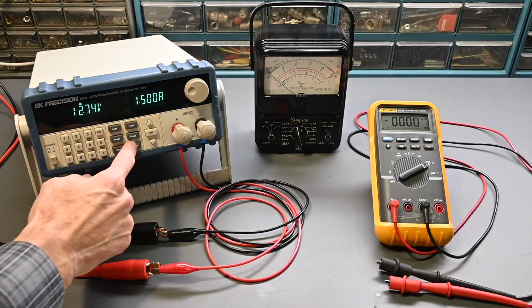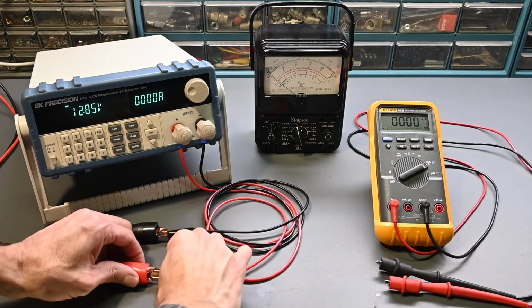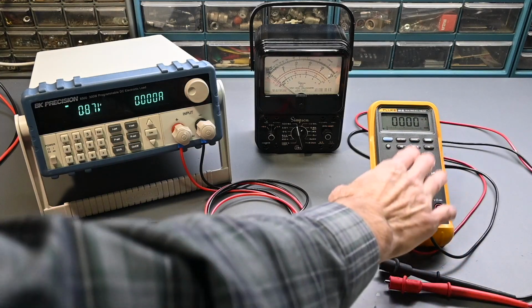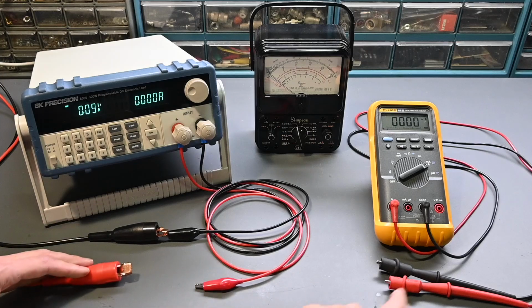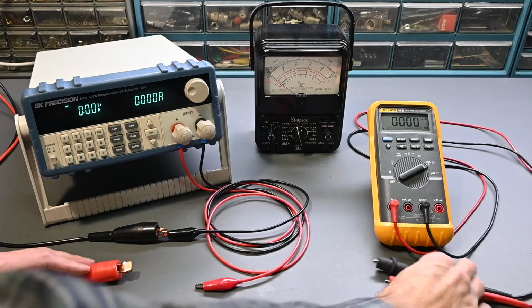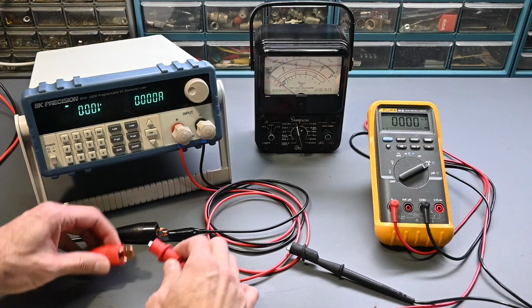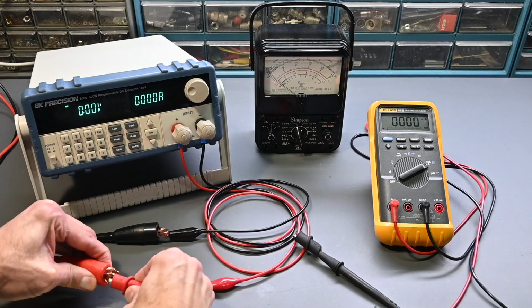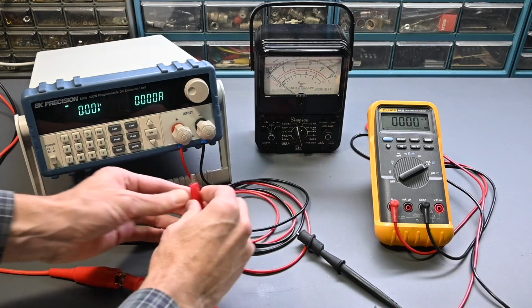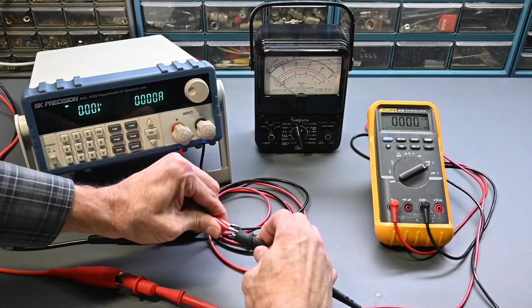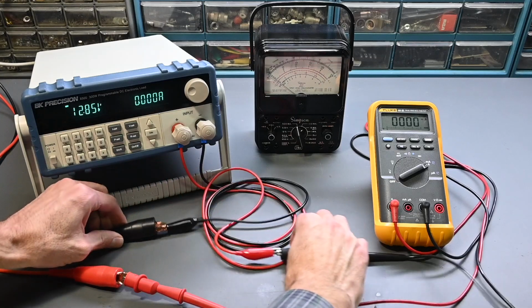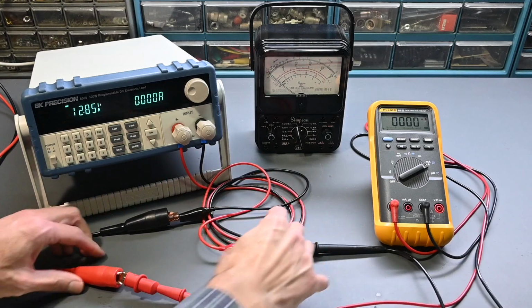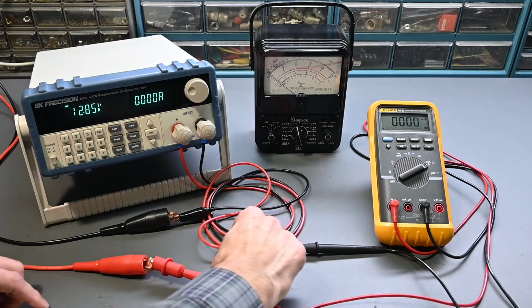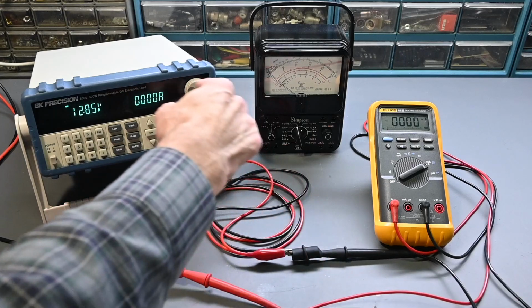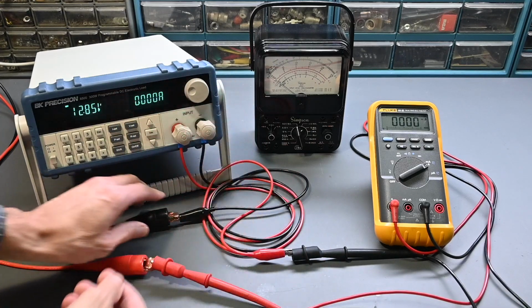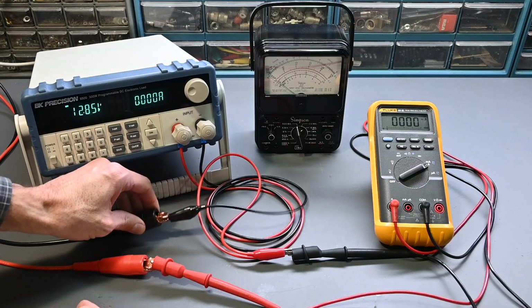I'm just going to turn off this electronic load for just a second. So you have to break the circuit, and the meter needs to be put in series with the circuit. Now the correct polarity on these test probes is to take the positive test probe and connect it to the positive side of the power supply, like so. And then the other side goes to the negative, just like so. And this is more negative than this side right here because this side goes around through the circuit, in this case the electronic load, and then returns out to the power supply's negative.